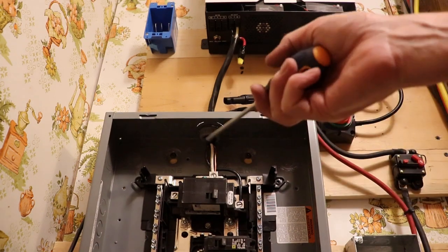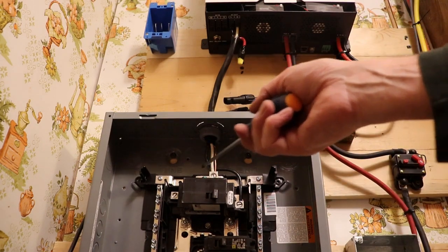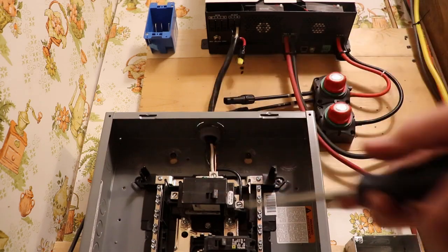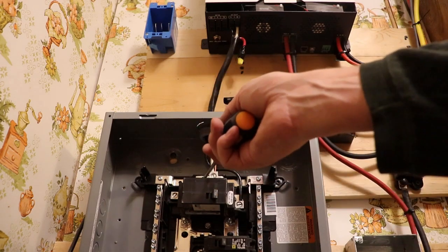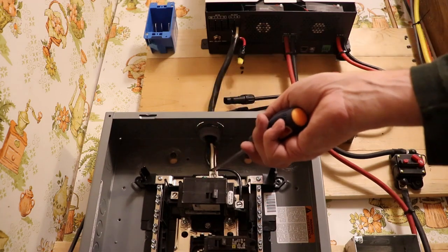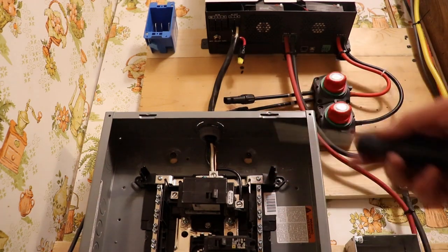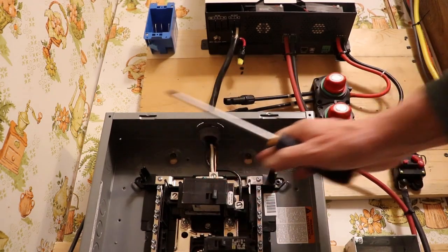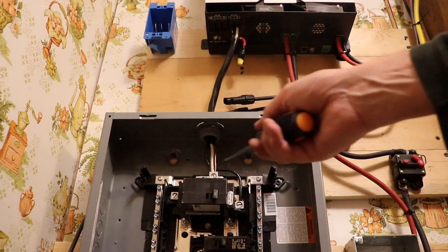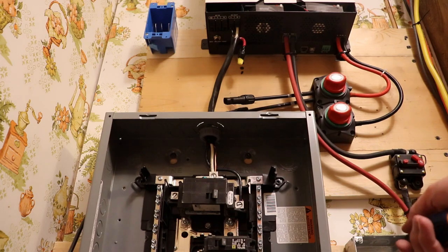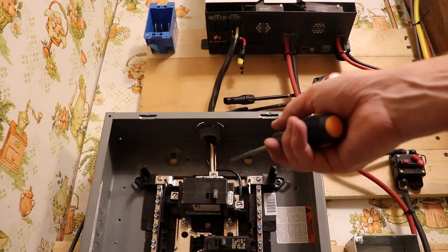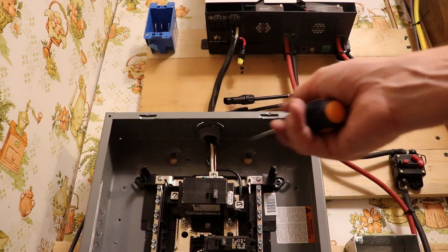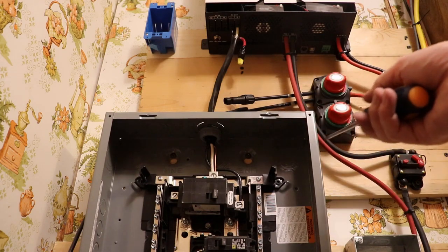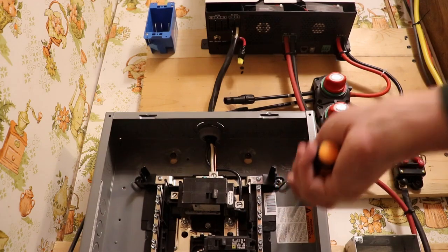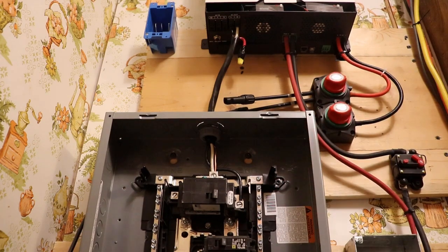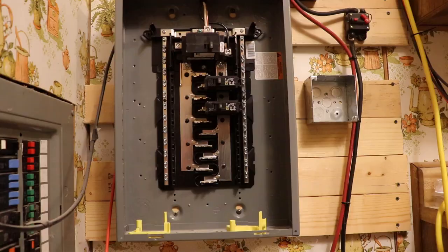The reason we put the neutral and ground here is because we use this bar. You apply this if you're going to use the ground and neutral in the same bar, and you only do this on the main panel. If I put a sub panel on, the ground will go to the box, not to the neutral bar. Just a little follow-up on that.